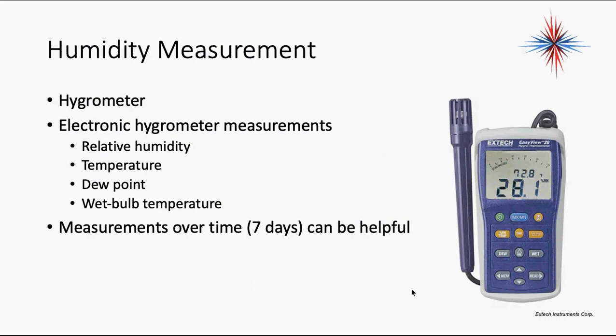Humidity measurements are done with a hygrometer. Those with the newer tools have a little yellow tool in your toolkit—that's a hygrometer measurement. Those with the older toolkits have to take a wet dry bulb thermometer reading, and you can come up with the relative humidity. Hygrometer measurements give you relative humidity, temperature, dew point, wet bulb temperature—same as that little yellow tool.